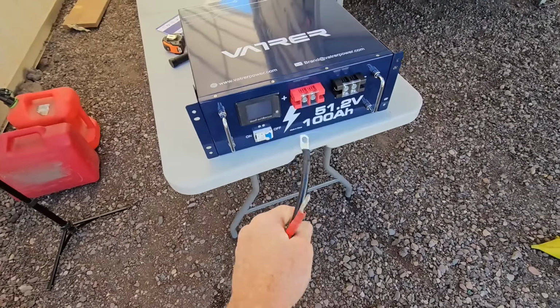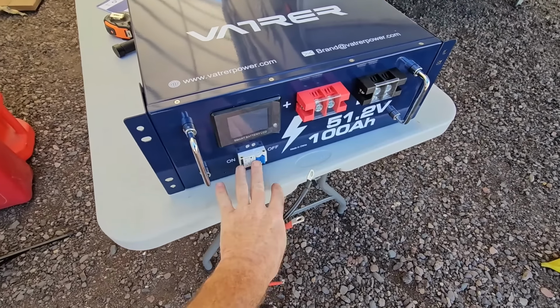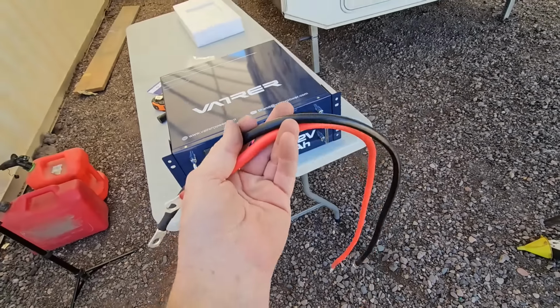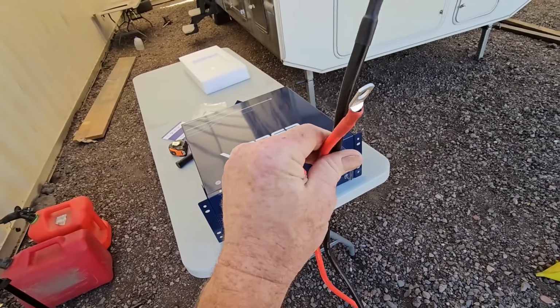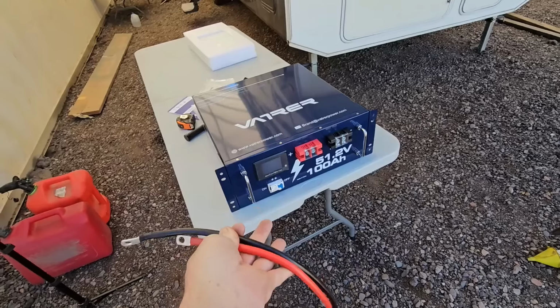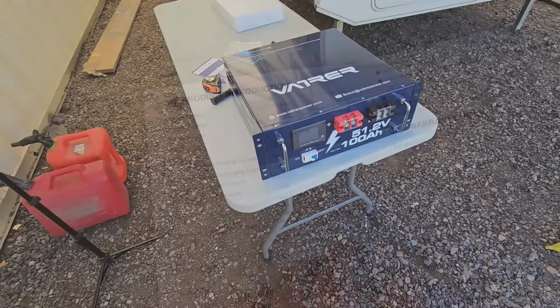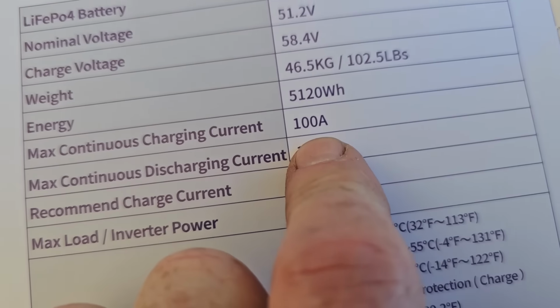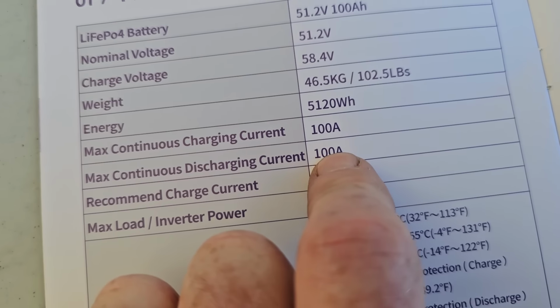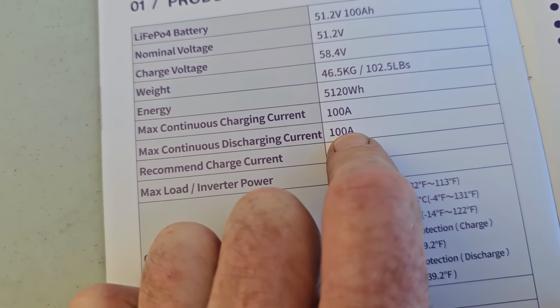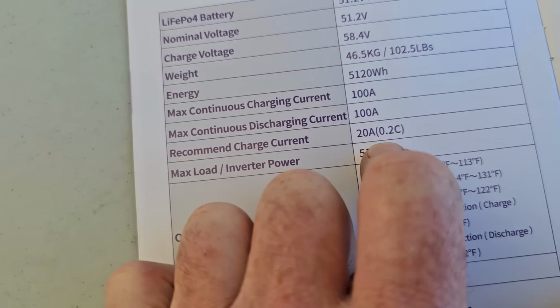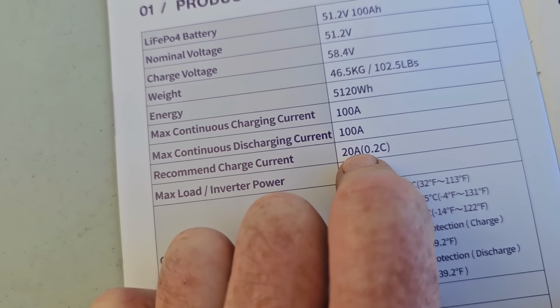So it's not going to trip until 125 amps are going through it. That means they could expect these little tiny 4 or 6 gauge wires to handle about 125 amps. So it looks like its maximum continuous charging and discharge current is about 100 amps, so 125 would be pushing it. And recommended charge current is 20 amps.